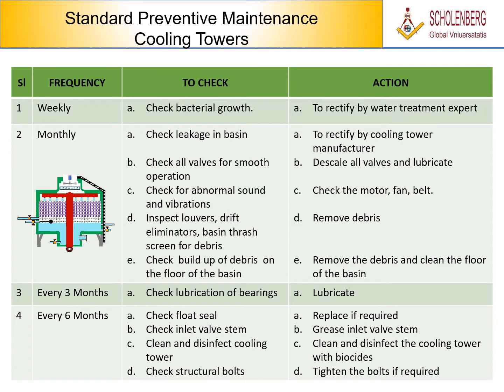Standard preventive maintenance. Cooling towers. Serial number. Frequency. To check. Action. 1. Frequency, weekly. To check, bacterial growth. Action, to be rectified by water treatment expert. 2. Frequency, monthly. To check. A. Check leakage in basin. Action. To be rectified by cooling tower manufacturer. B. Check all valves for smooth operation. Action. Descale all valves and lubricate.